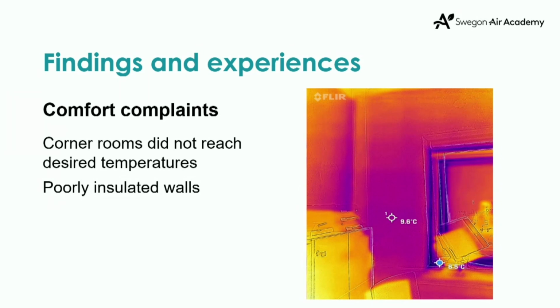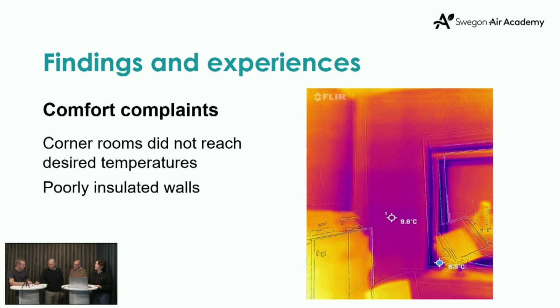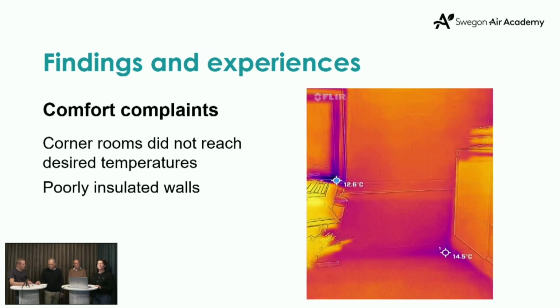So how did you finally solve this? We helped find a solution by adjusting the settings for the comfort modules in those rooms. We raised the temperature set value and increased the airflow in the rooms. Now the comfort is within values, and we saved extra cost for the property owner, and we can also inform the tenant of the cause and what we've done to solve it.